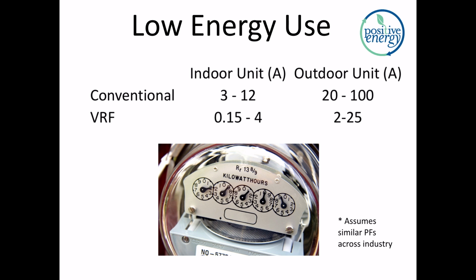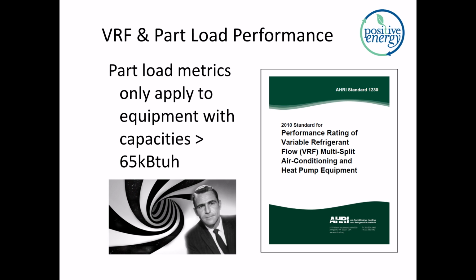So let's talk a little bit about efficiency. I mentioned that 30 SEER. SEER is rating equipment at 1 load factor, and it's full load. AHRI has a standard. There's standard 1230 2010 for the performance rating of VRF equipment. I encourage you to look at this. In that standard, they essentially say that they expect the full capacity rating to be valid for around 2 to 3% of the hours of the year. And other than that, you're going to be looking at part load metrics, which are going to be in play.